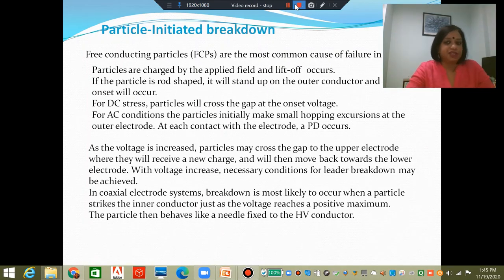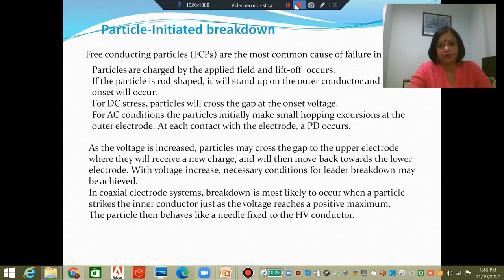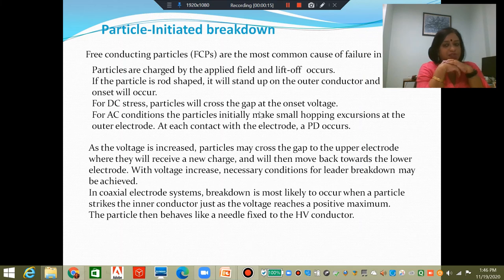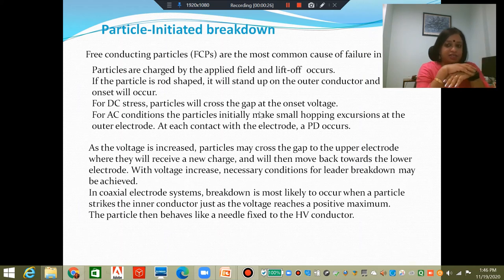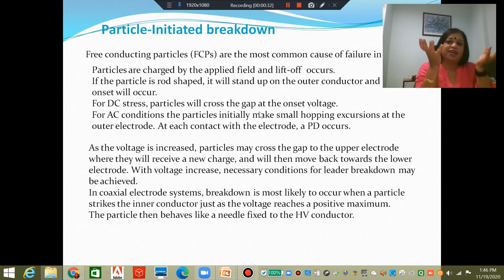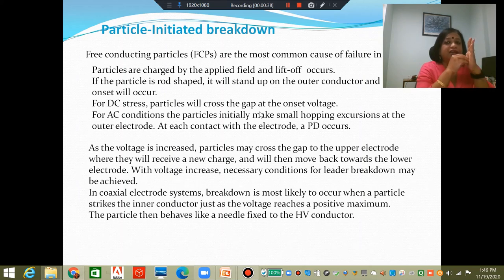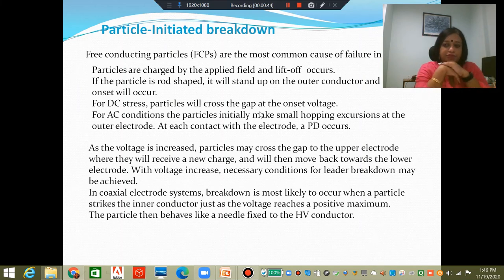Apart from that, there is another breakdown mechanism very likely in GIS which has not been discussed before: particle initiated breakdown. Free conducting particles (FCP) are the most common cause of failure in gas insulated substations. Despite actions taken by the manufacturer and despite the clean environment in which manufacturing and assembly takes place, there is still the possibility of free conducting particles produced by assembly and manufacturing processes remaining within the encapsulation.